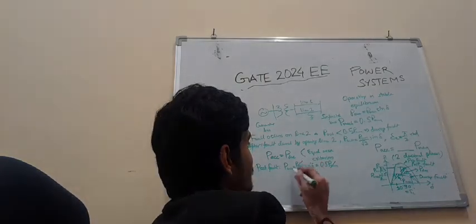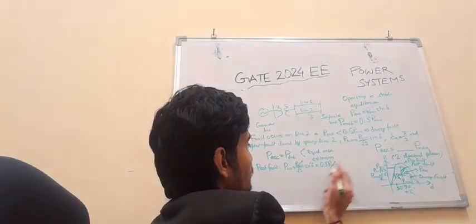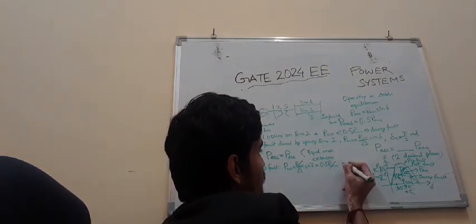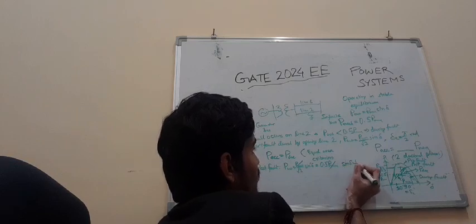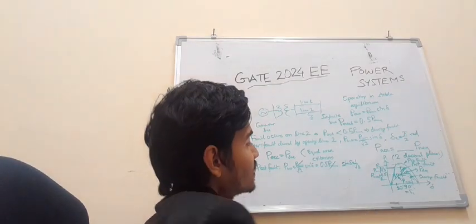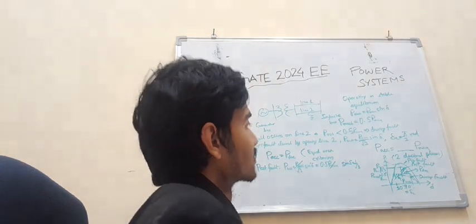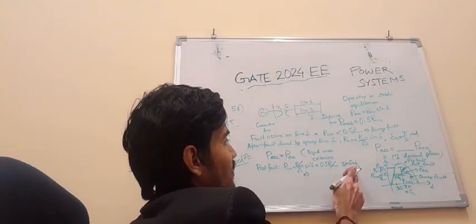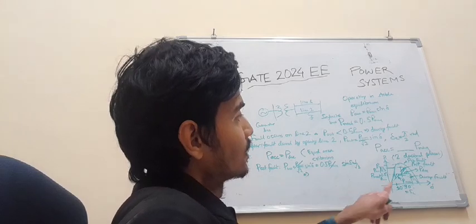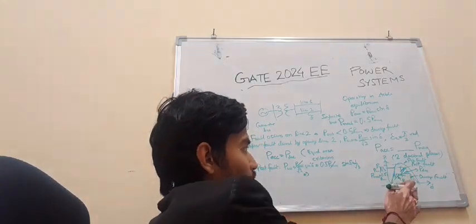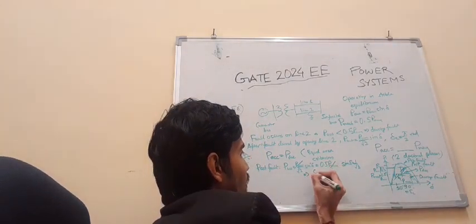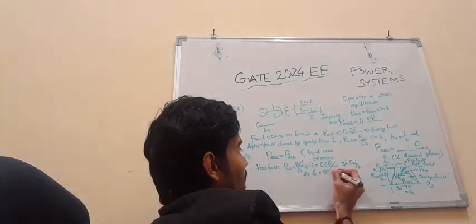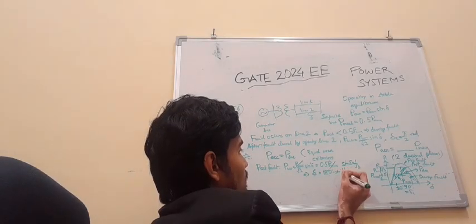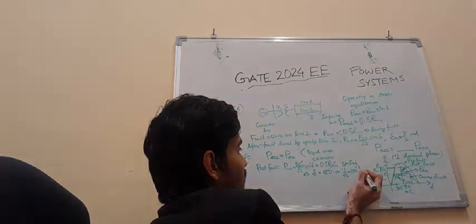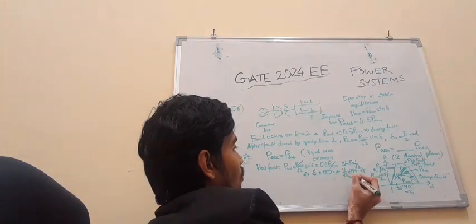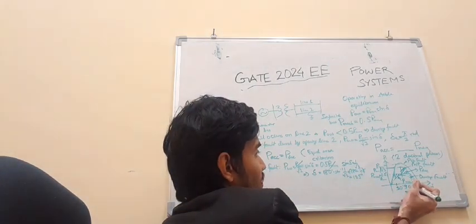P max cancels, and taking it to the other side we get sin delta equal to 1 by root 2. Since delta lies between 90 and 180 degrees, sin inverse of 1 by root 2 is 45 degrees, but to keep it in range we take delta equal to 180 minus 45, that is 135 degrees. So this angle is 135 degrees.